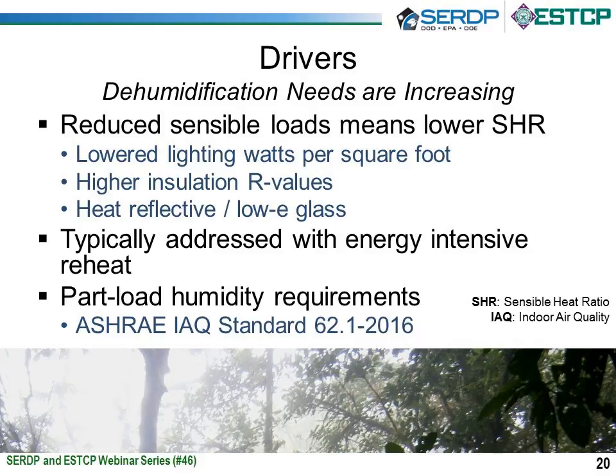Another driver of improved DX technology is dehumidification needs. Dehumidification has become much more important over the past several years. There are really 2 or 3 reasons for this. One is that reduced sensible loads mean a lower SHR, sensible heat ratio. What's happening is that as buildings are becoming more efficient, and lighting is becoming more efficient, and glass is more energy efficient, those technology improvements are addressing the sensible, or the dry heat load. SHR is the ratio of the dry heat load to the total heat load, or the total amount of cooling that the air conditioner has to provide.